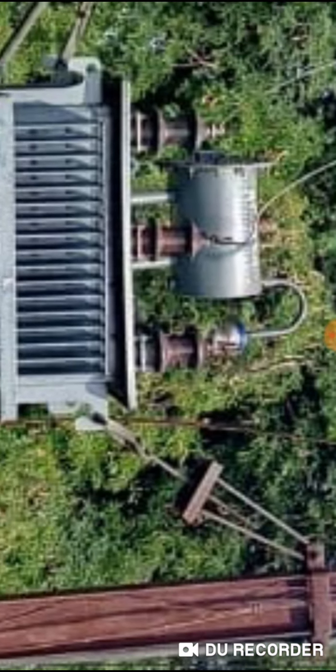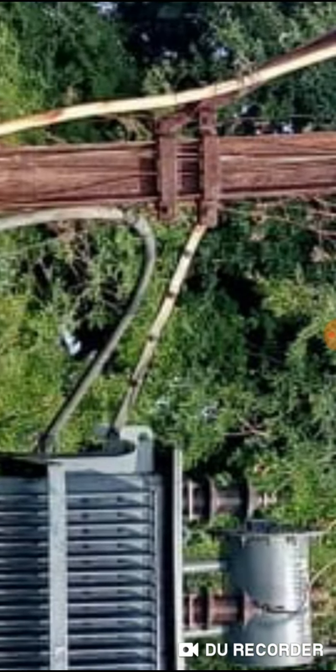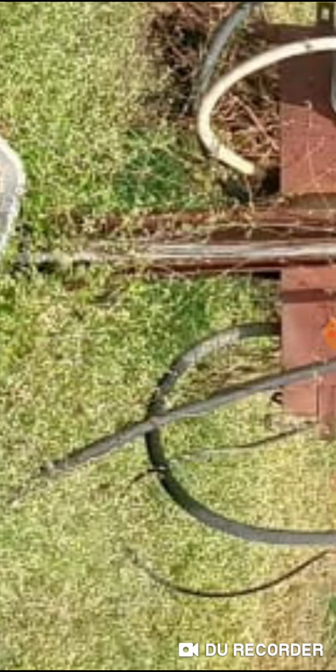Please see. Now, this side, the transformer is hung only on the turnbuckles. And as usual, there is a lot of greenery at the bottom. If somebody walks up and drops a spanner, etc., it will be a heavy search to find it. Hence, around the DP, a 10 feet by 10 feet area must be very clean for proper working.